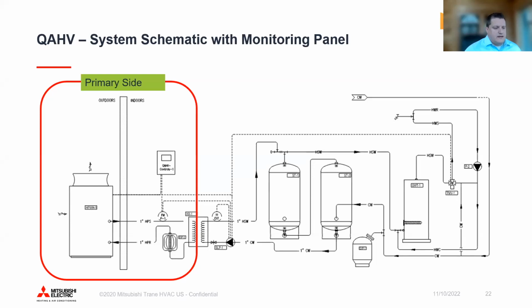One, because it prevents having to do maintenance on the actual heat pump itself, where that heat exchanger is going to have CO2 on the other side. But two, it will allow us in the near future to also do glycol on this primary side for all the cold climates that are on the call. It will help us have another option from what we're currently doing, which is basically heat tracing that piping out to the heat pump.